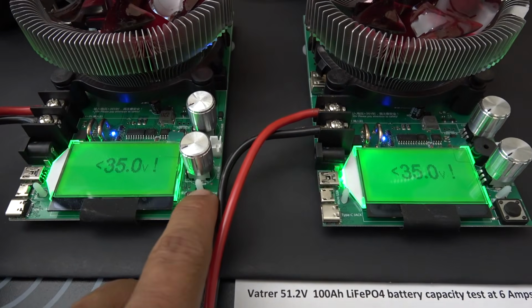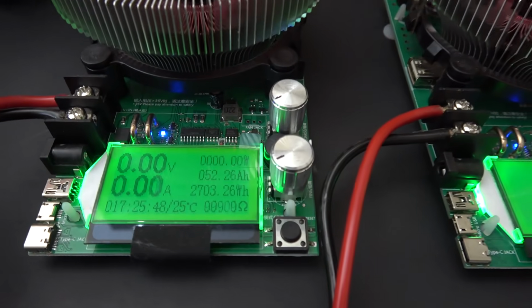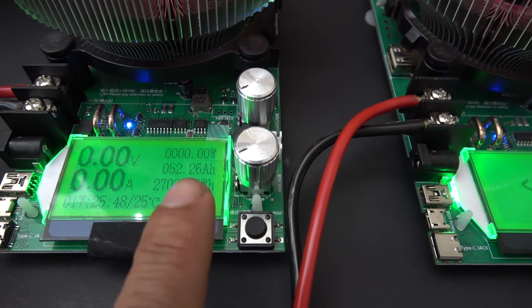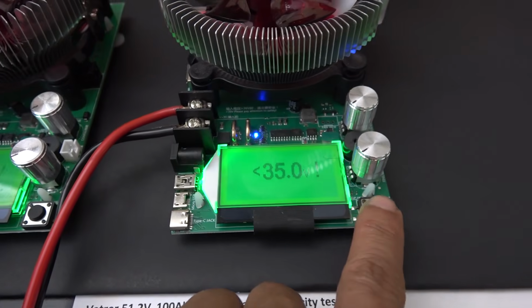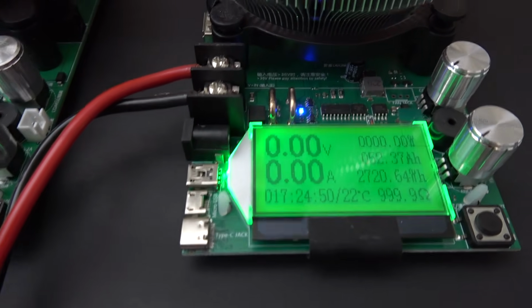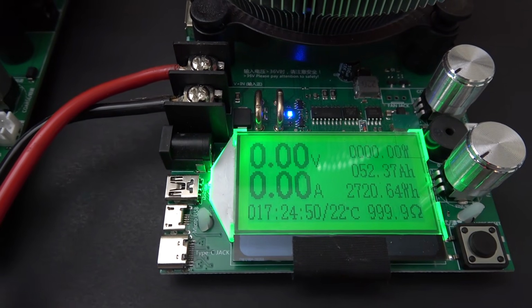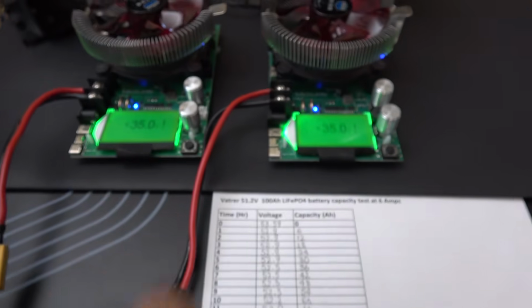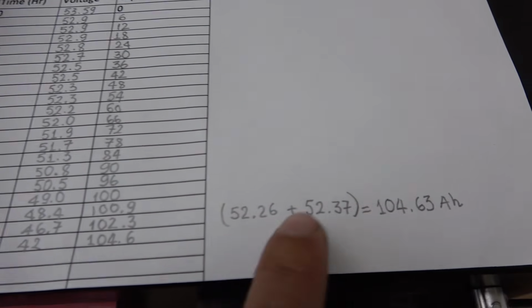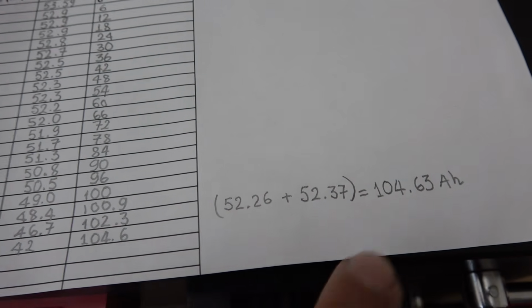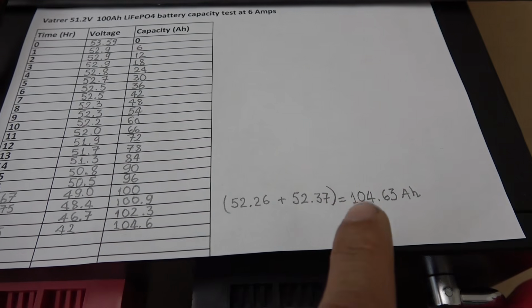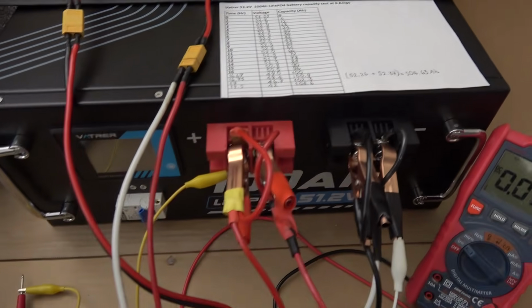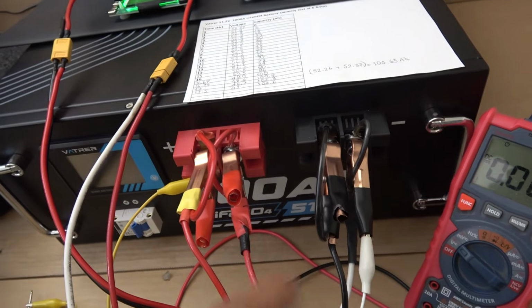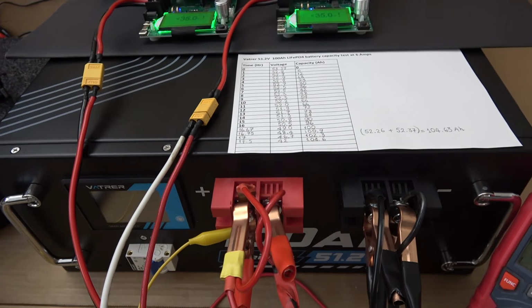And let's see what we got. The one on the left, we got 52.26 amp hour. The one on the right, 52.37 amp hour. So the total capacity of the two is 104.63 amp hour. And that's almost 5% more than the 100 amp hour rated capacity for this battery. That's awesome.